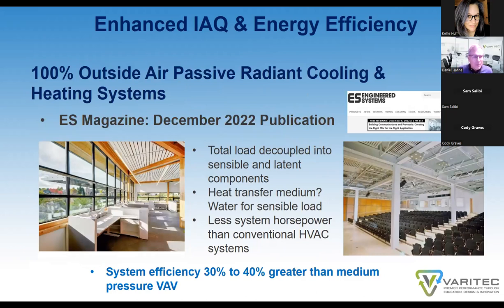In December, I evaluated another system, a 100% outside air passive radiant cooling and heating system. This is where the sensible load of a building is actually drawn to a chilled water loop local to each zone, and we bring only 100% outside air to a space.